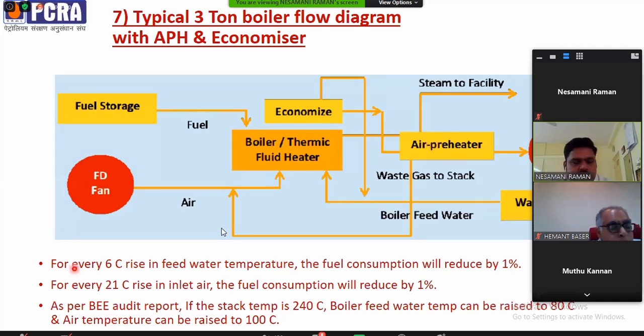The standard is that for every 6 degrees Celsius rise in feed water temperature, the fuel consumption will reduce by 1%. Here for the boiler, we give boiler feed water. PCRA has done energy audits of rice mill clusters in Tamil Nadu. We observed that they also do not have an air preheater and economizer. The boiler feed water used to be sent at normal temperature. Instead, if you increase the temperature by 6 degrees Celsius, fuel consumption will reduce by 1%. For air, if you increase the air temperature by 21 degrees Celsius, the fuel consumption will reduce by 1%.